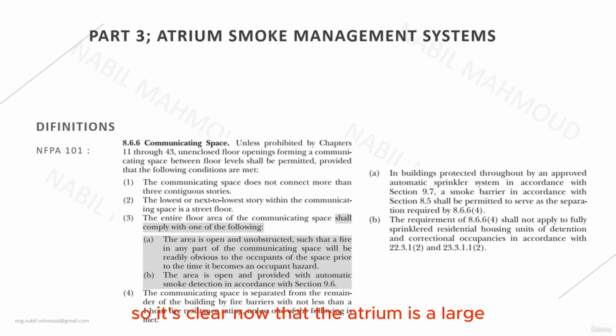So it's clear now that the atrium is a large vertical volume enclosure that connects more than 3 floors or more than 3 stories high. However, the communicating space is limited to only 3 stories high.